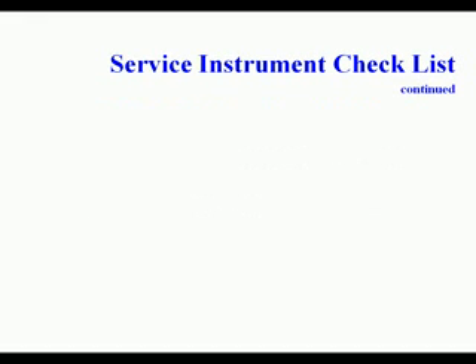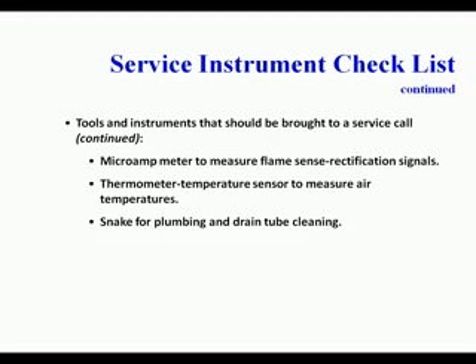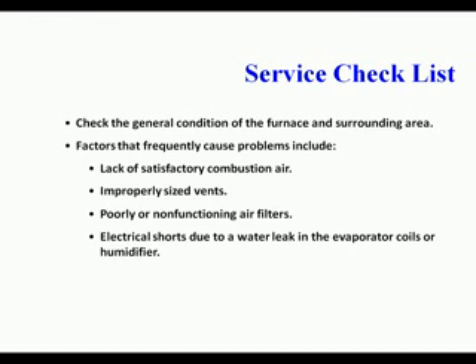What you need to service equipment: you should have an inclined manometer, 0 to 3 inch range, to measure heat exchanger pressure drop. You should have another manometer, 0 to 1 inch range, to measure duct static pressure. You should have a U-tube manometer to measure gas pressures. You should have a volt and ohm meter. You need to have a microamp meter to measure flame sense rectification signals. You must have a thermometer or temperature sensor to measure air temperatures. You should have a snake for plumbing and drain tube cleaning, and you should have a small inspection mirror.